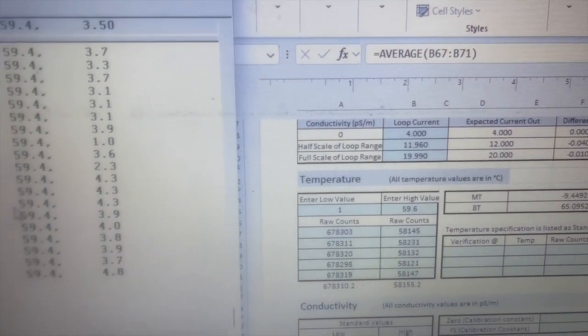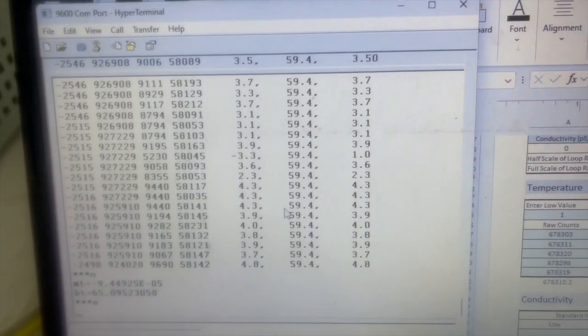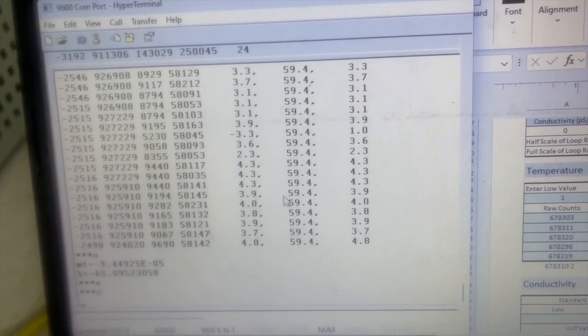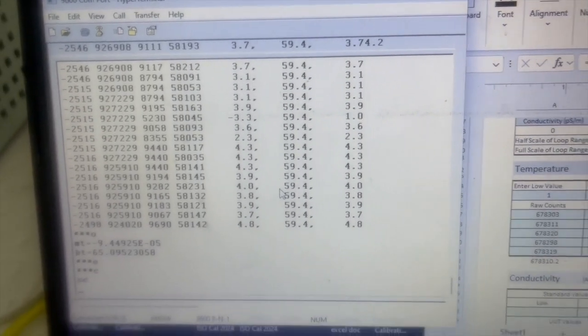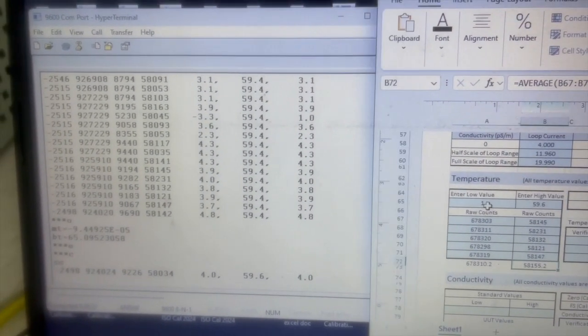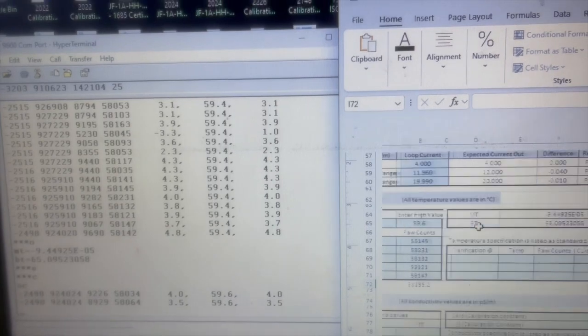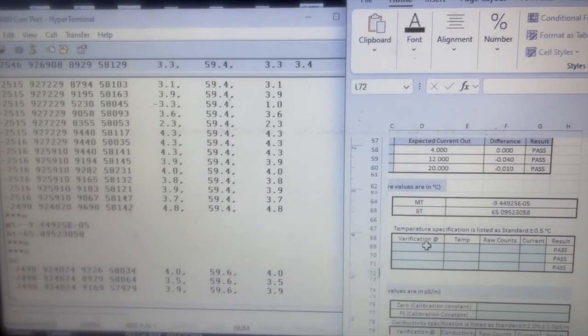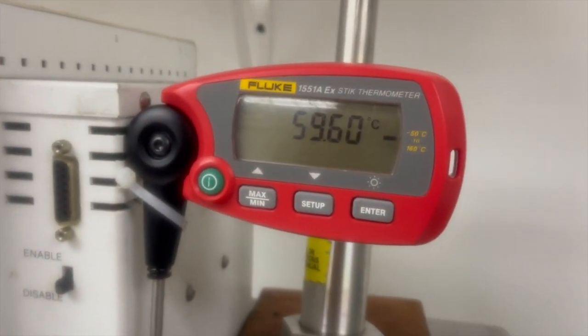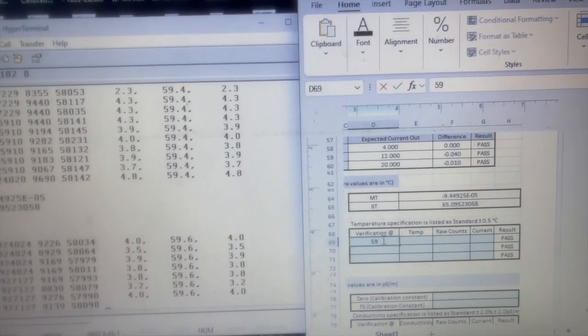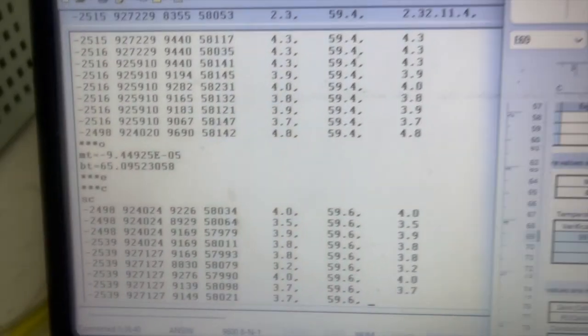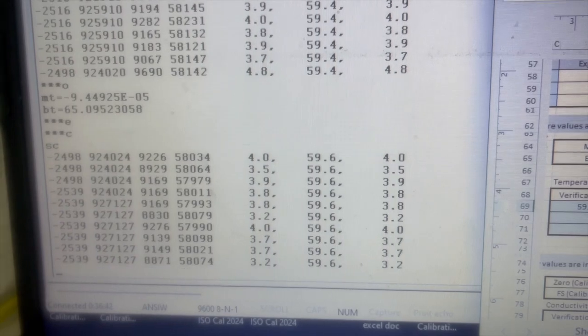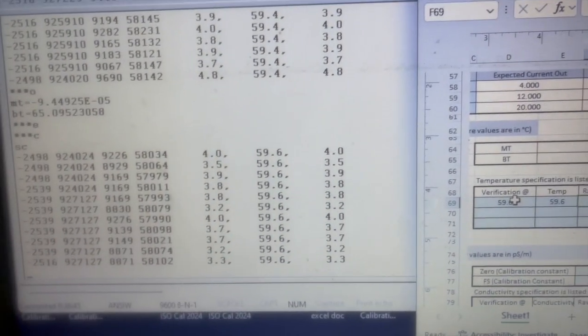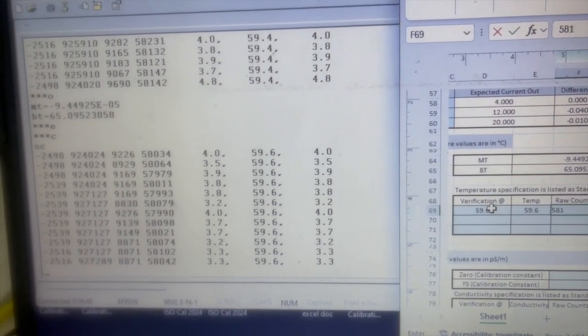Okay, once you've done that, you're going to go ahead and put the sensor back into calibration mode. We're going to verify that the sensor is reading the temperature correctly. So we're going to go over here and we're going to get our measurement from our temperature probe, which is still 59.60. So 59.60. And then our sensor's reading 59.6. And the raw counts are 58,102.